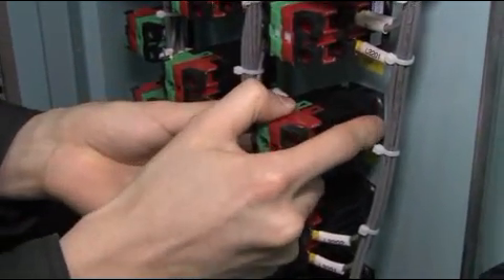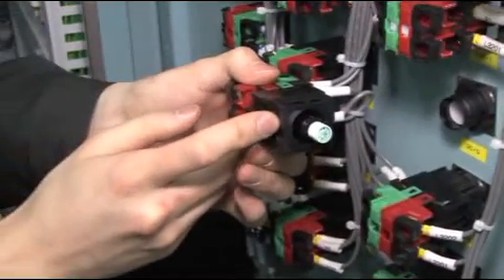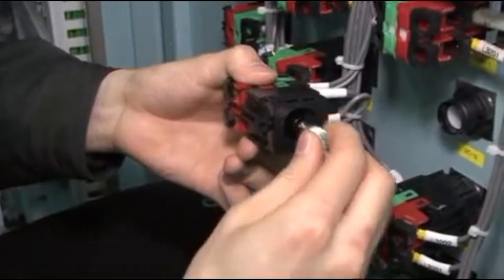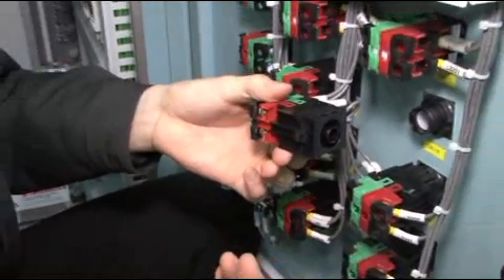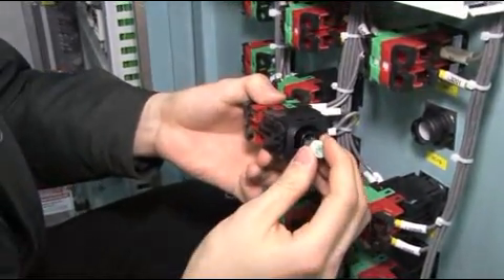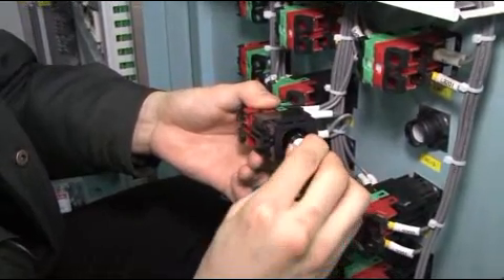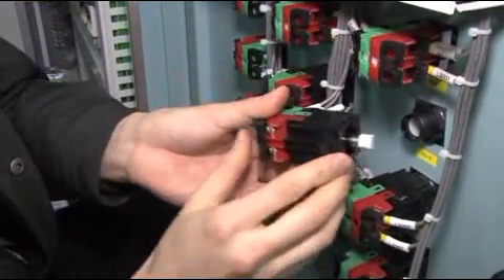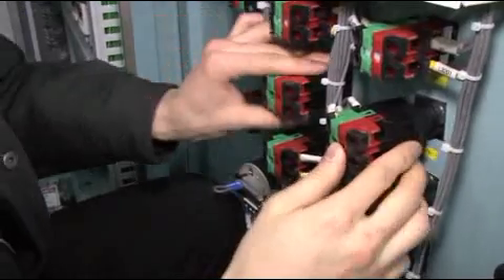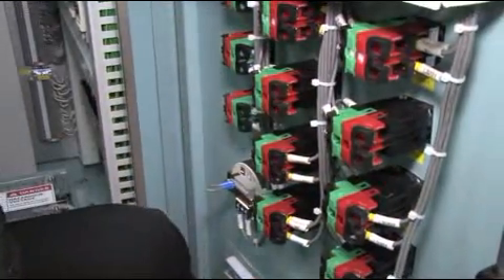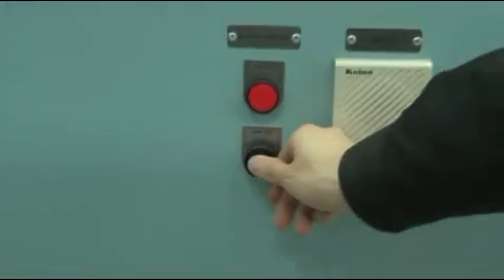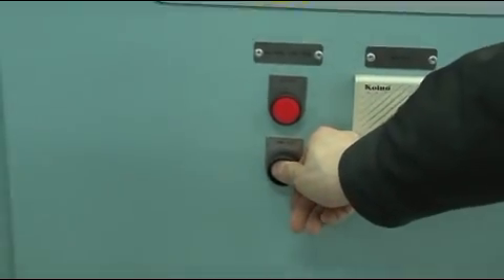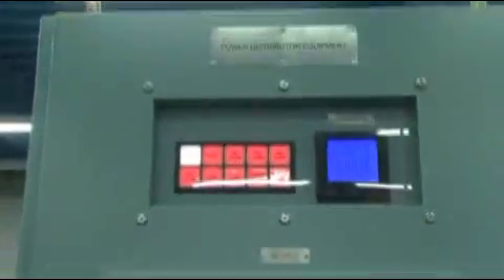Lamp bulb. Applicable equipment and location, PDE. Step 1. Take apart the power part of button lamp and remove the defective lamp by turning to the left. Step 2. Remove the defective lamp by turning 90 degrees to the left while pressing inward. Step 3. Check color and voltages of a new lamp and replace it, following instructions in reverse order from Step 2 to Step 1. Step 4. After the power is on, check operation of lamp. Lamp light.